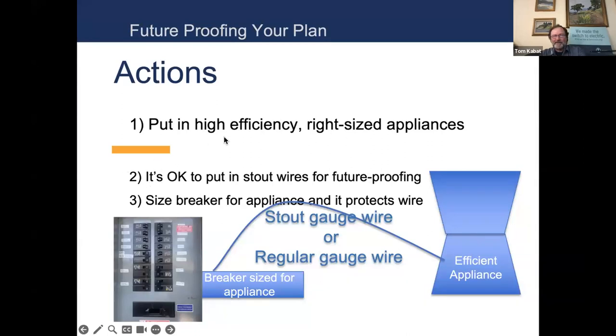The other thing about using high efficiency equipment is it's okay to put in big stout wires, like putting in 50 amp wire when installing a 20 amp car charger. You'd use the 20 amp car charger with the 50 amp stout wire and a 20 amp breaker. So the breaker and the appliance are sized for each other, and they're also sized so the breaker is small enough to always protect the wire. That's a form of future proofing - just because you follow this watt diet approach doesn't mean you have to put in thin wires. You can put in thick wires, and it might save somebody else the expense of running wires if they have more opulent needs than you did.